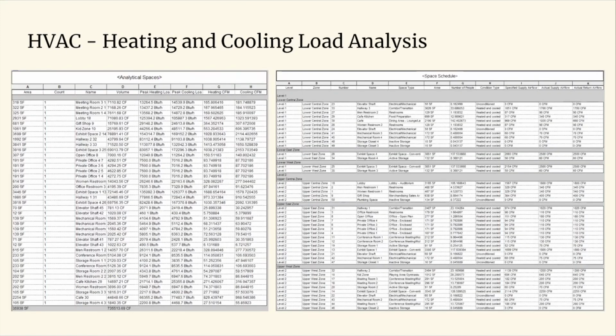While designing the heating and cooling system, I did a load analysis on the entire building by creating an analytical model. This gave me data on the peak heating and peak cooling loads the building will experience, and I actually designed the venting to meet the CFM for each room.